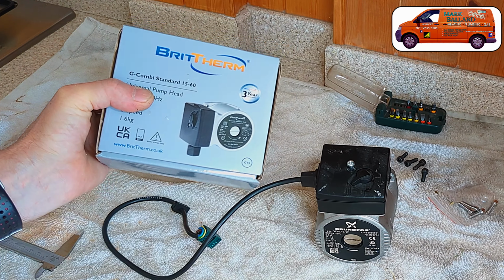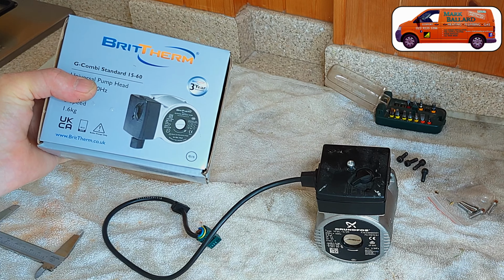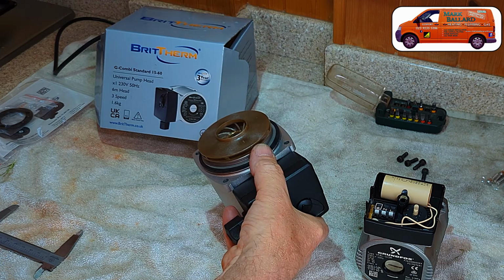£260. But I want to let you know that recently I used an alternative, which was a BritTherm pump head, and that fitted in the boiler a treat, and it's about a third of the cost of that Vaillant pump, and it does exactly the same job. If you want to know more about this alternative pump head, then make sure you stick around to the end of the video and I'll show you exactly how I went about fitting this pump head.